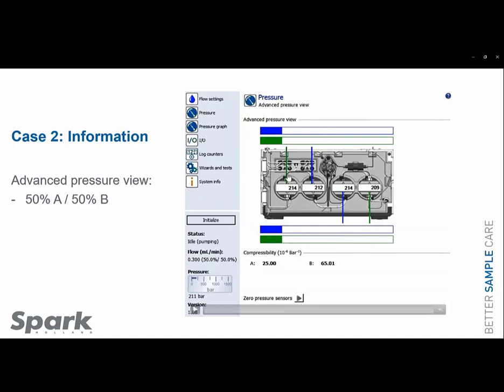Actually, this check valve should be closed. The outlet check valve should be closed. This should be 6 bar below the system pressure, right? And it's not even calculating any compressibility. The problem is in pump A.